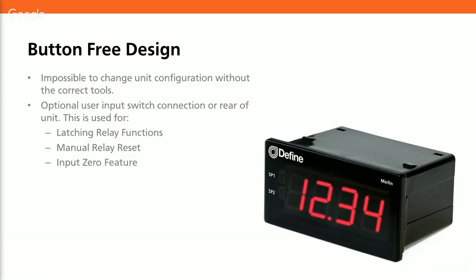The Merlin does have an optional input switch connector on the rear of the unit that is fitted on models that have the relays and analog output installed. This switch is used to reset relays when they are set up in a latching mode. It's also useful in situations where you want a manual reset of the alarm. The manual reset disables the alarm until the unit has returned to its no-fault state. This is great for silencing an annoying buzzer.